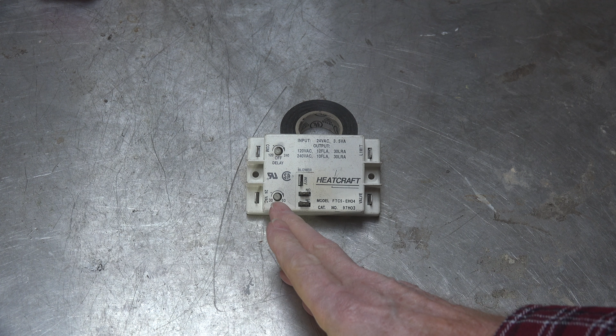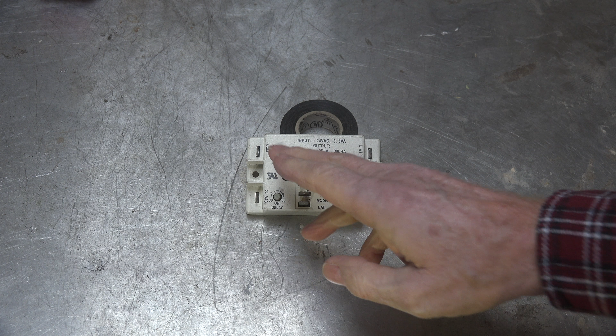The off delay is what keeps the fan operating after the burner's shut off, to clear the heat out of the heat exchanger. It also has a dot there, which is probably at about 3 minutes. Here again, what you're trying to do is keep the duct temperature warm. If you set this delay at, say, 120 seconds, I think it looks like the dot is about 160 or 180 seconds. You can put it to the dot to start with. That's what most of them are set at. But if it shuts off at 120, you may be leaving an awful lot of heat in the ductwork.